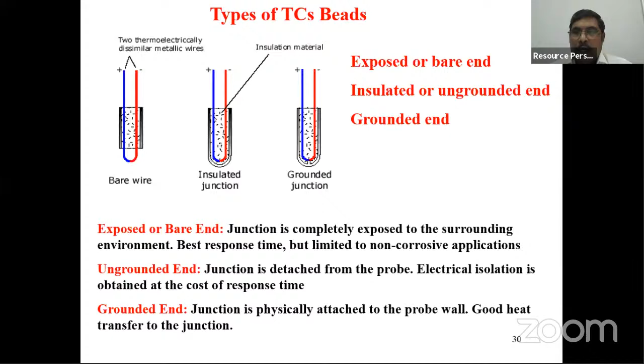Whenever you go for temperature measurement where electrical circuit interference is there, you must go for the ungrounded junction. In the ungrounded junction, inside this capsule, you fill magnesium oxide powder, because magnesium oxide powder has very good thermal conductivity, but electrically it is an insulator. Okay. So these are the classes of thermocouple. You can find this in any textbook, like E, J, K, T, R, and S, etc. Each thermocouple has its own temperature range. You can see the respective temperature range.